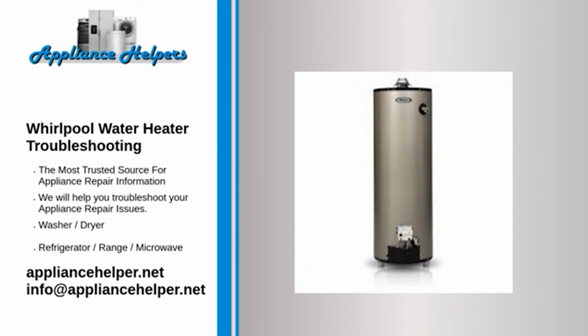Step 5. Troubleshoot water heaters that put out cold water. Check the power running to the upper element. If the voltage tester shows power, but the element is not heating, then the element is bad. If there is no power coming to the element, then the thermostat has failed and must be replaced.